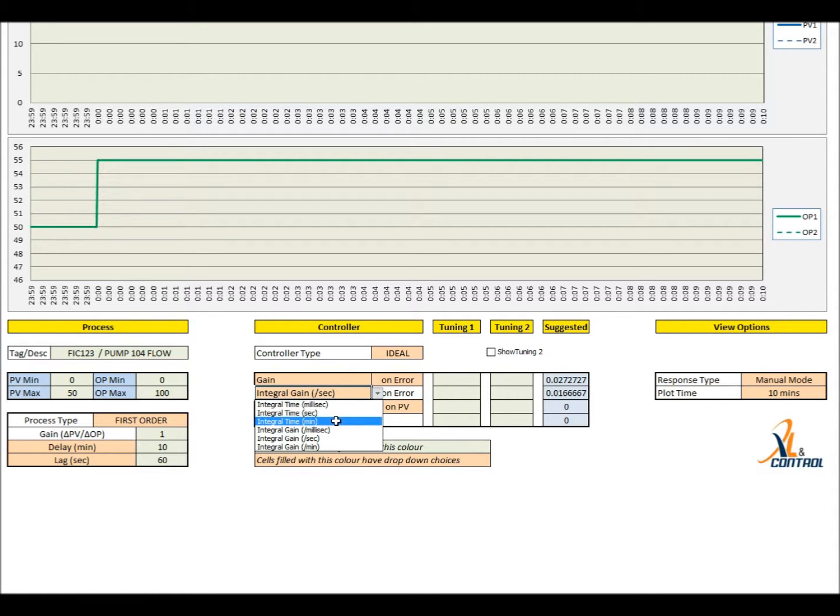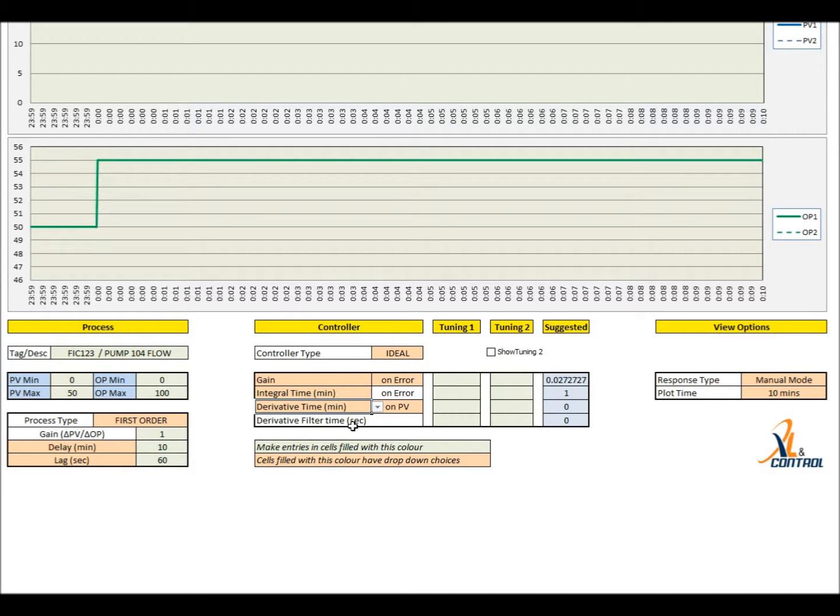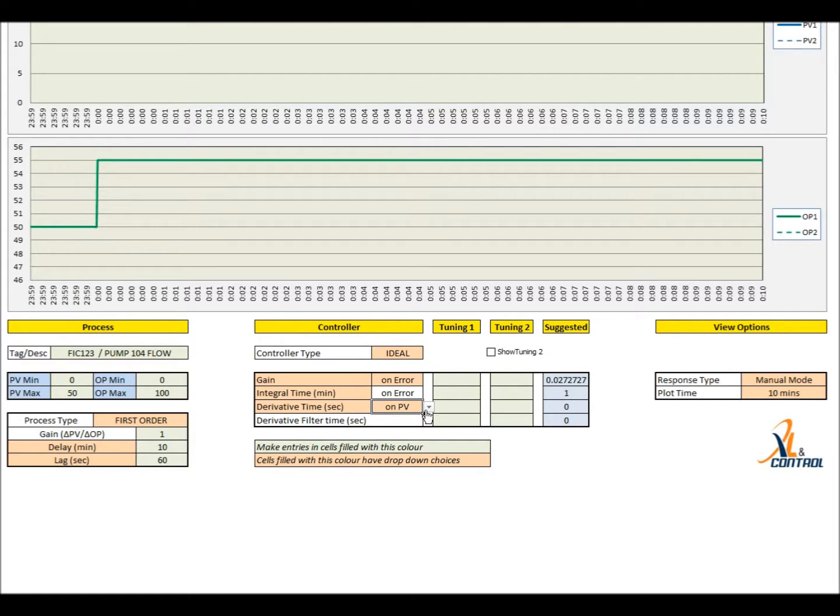Derivative time can be provided in milliseconds, seconds or minutes. First order derivative filtering is also supported. Choose derivative action on error or on process value.